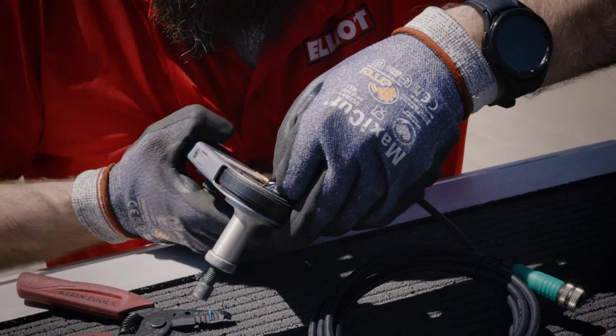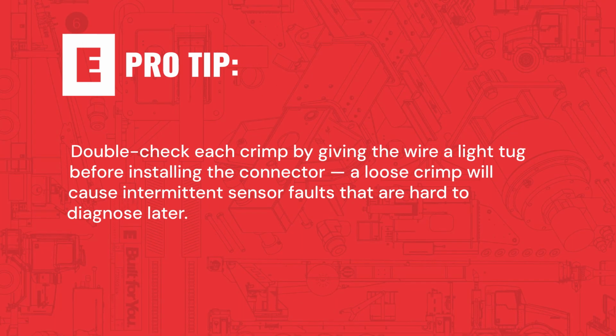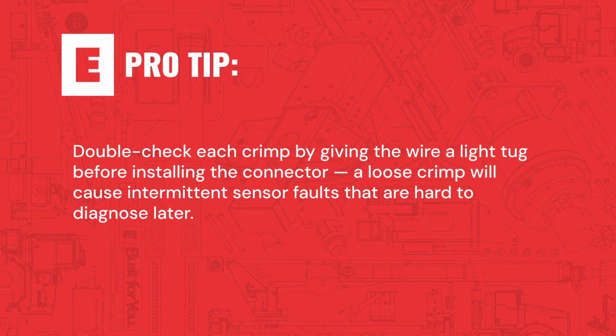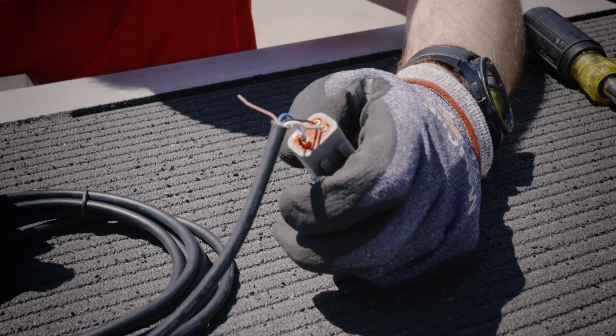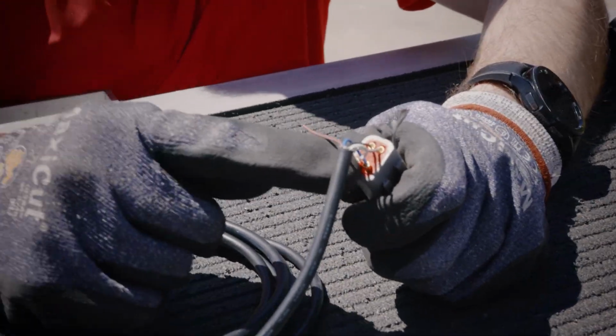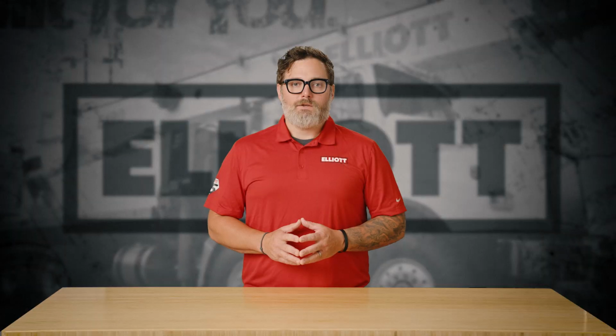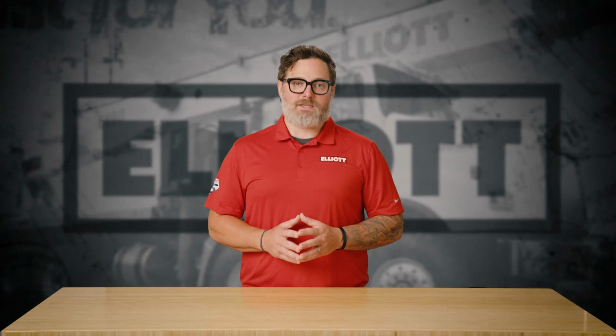Once all 4 wires are terminated, install the cable and route it cleanly along the boom. Pro tip: double check each crimp by giving the wire a light tug before installing the connector. A loose crimp will cause intermittent sensor faults that are hard to diagnose later. The brown wire is not used. Cap or insulate it to prevent any chance of a short. This is an important step, so do not skip it.